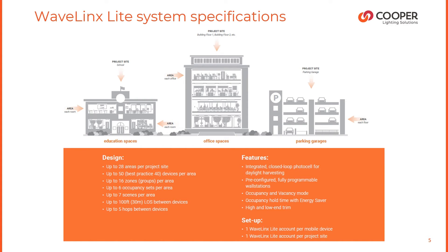Let's take a look at the WaveLinx Lite system specifications. Starting in the bottom left corner, there is a new term specific to WaveLinx Lite: project site. Once we initiate our project site, that gives us the capability to have up to 28 areas. An area is a space with devices that are going to act together — that could mean a conference room, a classroom, a floor of a parking garage, or an open office space. In any area, you have up to 50 devices, with best practice being 40 devices. We never want to fully load an area.